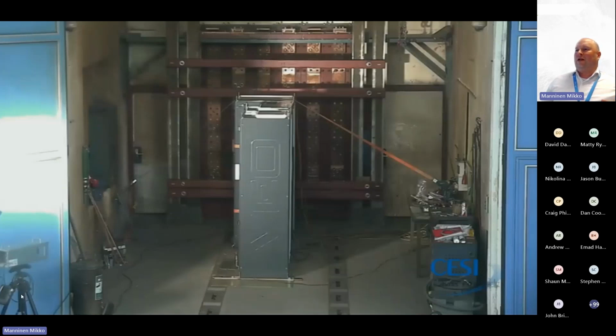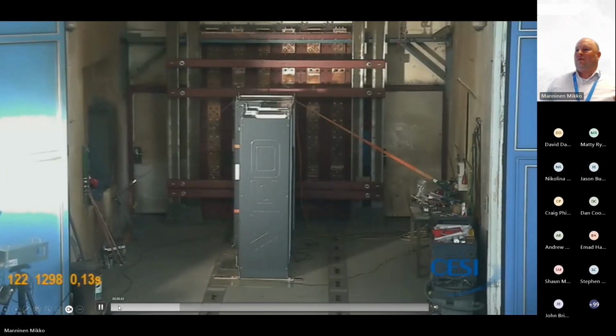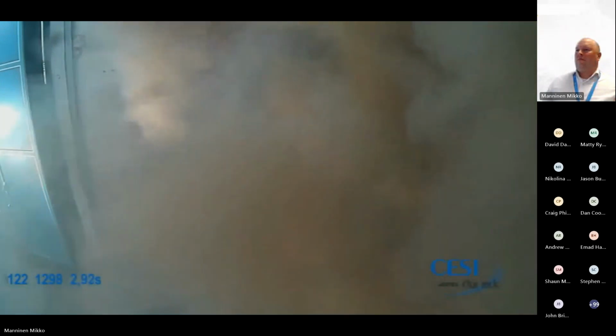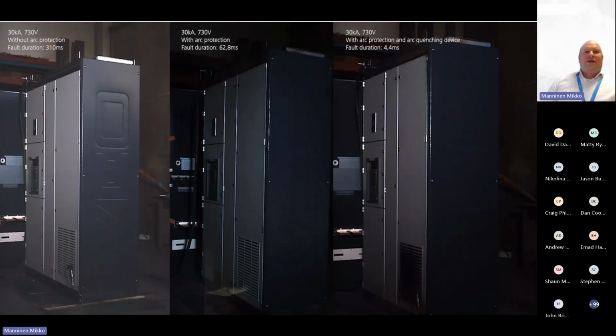This is the smallest power test we have done, and this is simulating the typical feeder protection. So let me run it. Imagine you saw quite a flash from here, but actually this test was a pass from the 61641 point of view. So the doors stayed closed, and it was actually a pass. But it looks very dramatic.